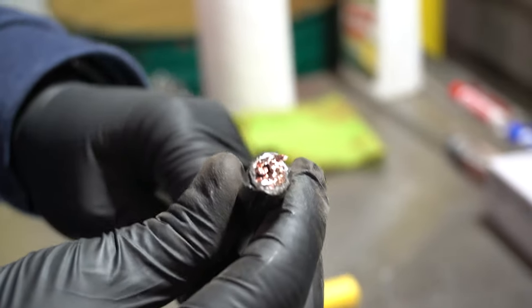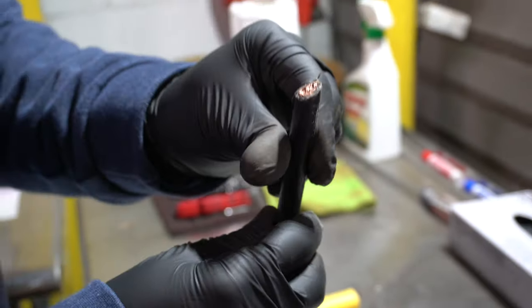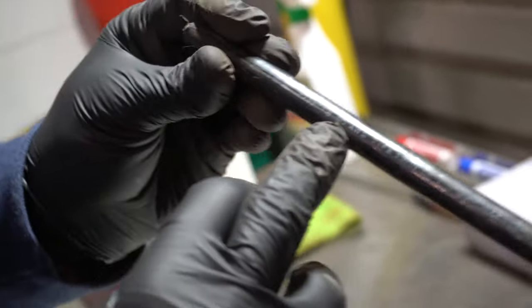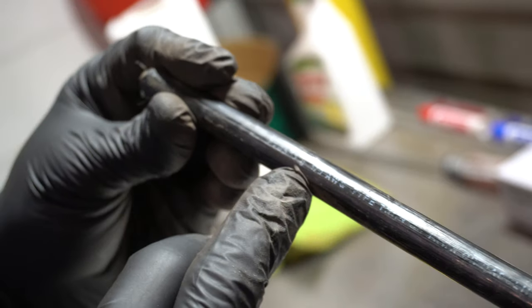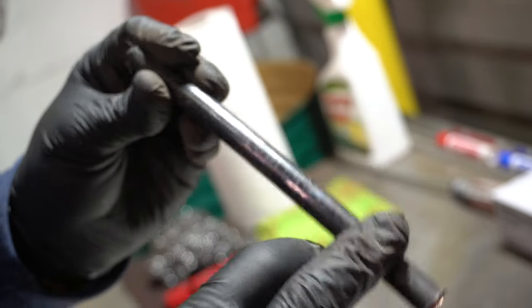Next up, we have about an 80 to 85 percent copper. Inside, it's going to be all bare bright. Sometimes on the side, you'll see what size it is, whether it's a 1-0 or 200 MCM or 250. Here, we have a 1-0 type THHN. This is going to go for a higher price than this THHN is because there's going to be more copper percentage versus this one.